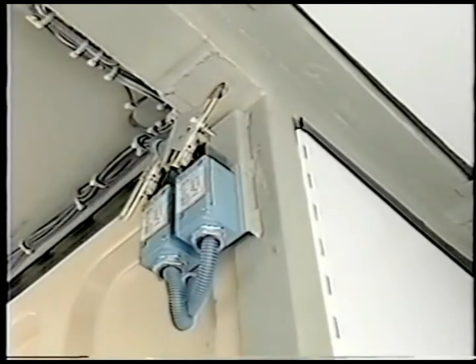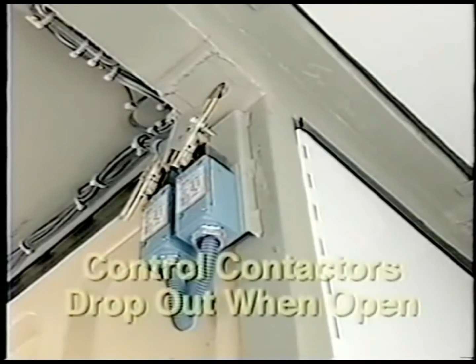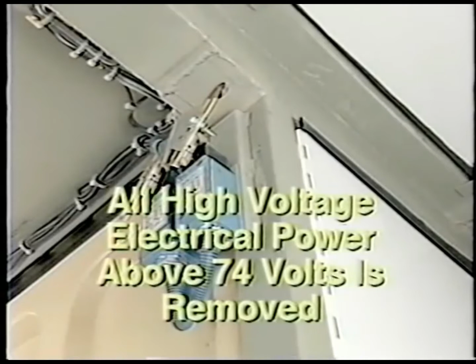The door interlock switch, DIS, is used for safety protection from high voltage in the auxiliary compartment. The door interlock switch opens with the door, dropping out the control contactors. The head-end power alternator, auxiliary alternator, and traction alternator unload. All high-voltage electrical power above 74 volts is removed.